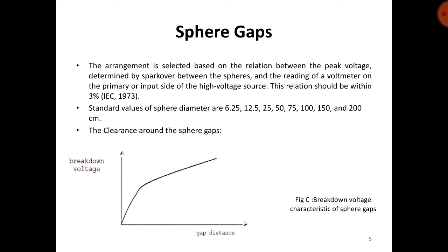The arrangement is selected based on the relation between the peak voltage determined by spark over between the spheres and the reading of the voltmeter on the primary or input side of the high voltage source. This relation should be within 3%. It is given by the IEC committee, so it is an international standard. Standard values of sphere diameter are 6.25, 12.5, 25, 50, 75, 100, 150 and 200 centimeter. These are the standard values for sphere diameter.